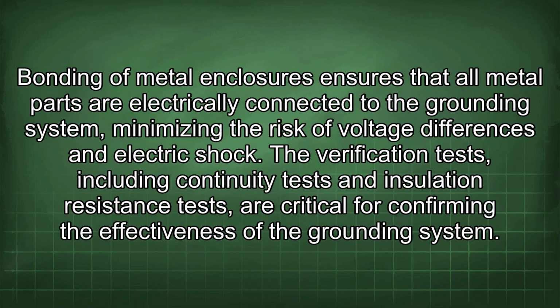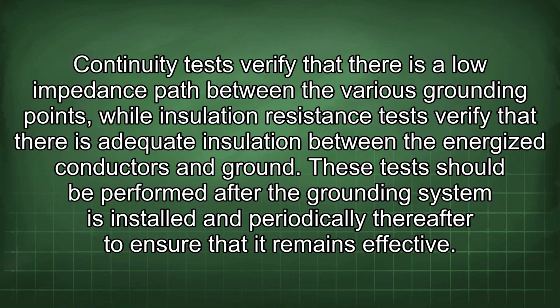Bonding of metal enclosures ensures that all metal parts are electrically connected to the grounding system, minimizing the risk of voltage differences and electric shock. The verification tests, including continuity tests and insulation resistance tests, are critical for confirming the effectiveness of the grounding system. Continuity tests verify that there is a low impedance path between the various grounding points, while insulation resistance tests verify that there is adequate insulation between the energized conductors and ground.